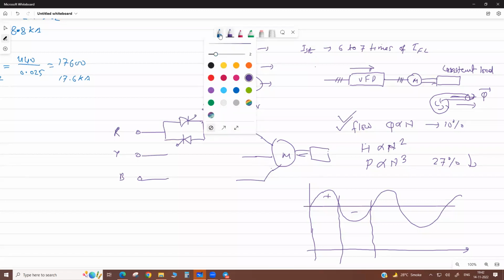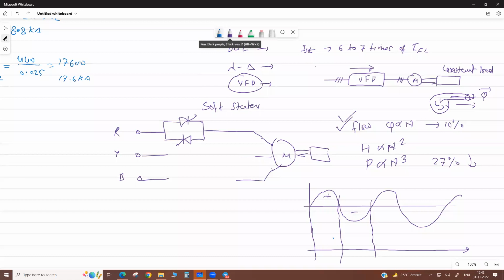We can control the firing angle. Like if we switch on here only, then we get this much voltage only. Here in negative, we increase this. So, okay, means we control. Now it is increased gradually. So actually your effective voltage to the motor is like this. We get a gradual rise to rated voltage. Then after the motor gets started and accelerated, we reduce the firing angle. This motor gets a rated input voltage, full voltage.